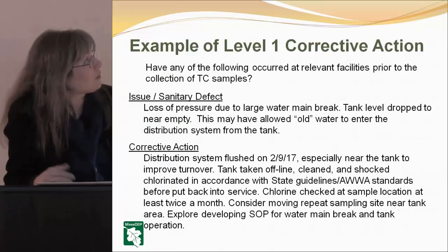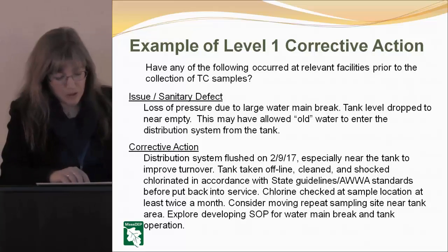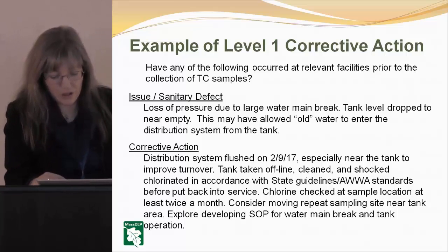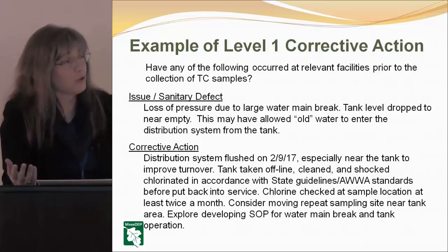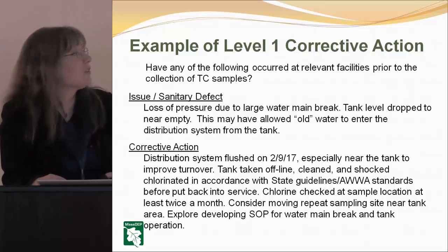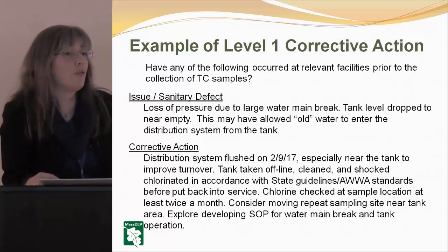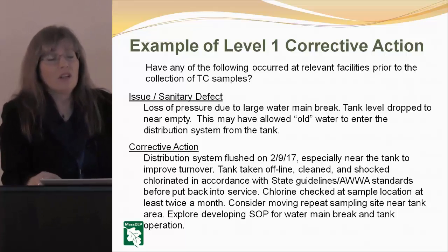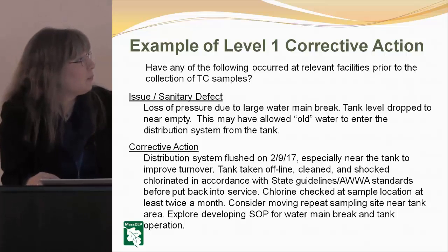Example of the corrective action. They're going to be reviewing what happened. Have any of the following occurred at the facility prior to the collection? Did you have a loss of pressure due to a large water main break? Did your tank levels drop to near empty? You may have had old water entering the distribution system from the tank. If you've had low turnover and then you have a sudden drawdown, you're not pulling the best water that you'd like out of your tanks.